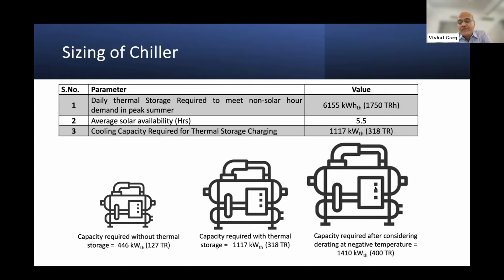And if we want to freeze ice and we have to go for a negative temperature of -5 degrees centigrade, then the derating happens and we need to further increase the chiller to 400 tons. So you can see that as compared to a regular chiller, there is much higher chiller capacity required if we want to charge the ice in the daytime in 5.5 hours.